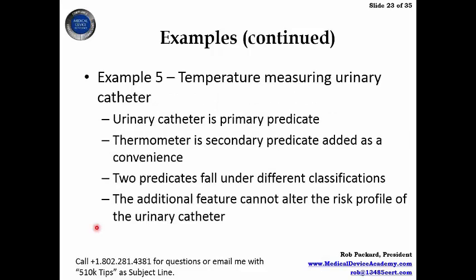And last but not least, we have a temperature measuring urinary catheter. The primary predicate is the urinary catheter, and then in this case, we have a secondary predicate, not a second predicate, but a secondary predicate. It's just for convenience. It's not the primary use, but it's a new intended use. It's to measure temperature. It doesn't need the same level of performance. This is how they recommend handling this type of example, where you put in a nice feature. A lot of cardiac monitoring systems will have calculators added in there, so somebody doesn't have to type it into a calculator. The computer actually does the work for them already. It might even spit out the answers of the most commonly requested physiological parameters that are calculated based on an input of, let's say, heart rate. Those are examples of a convenience feature that can be added on.